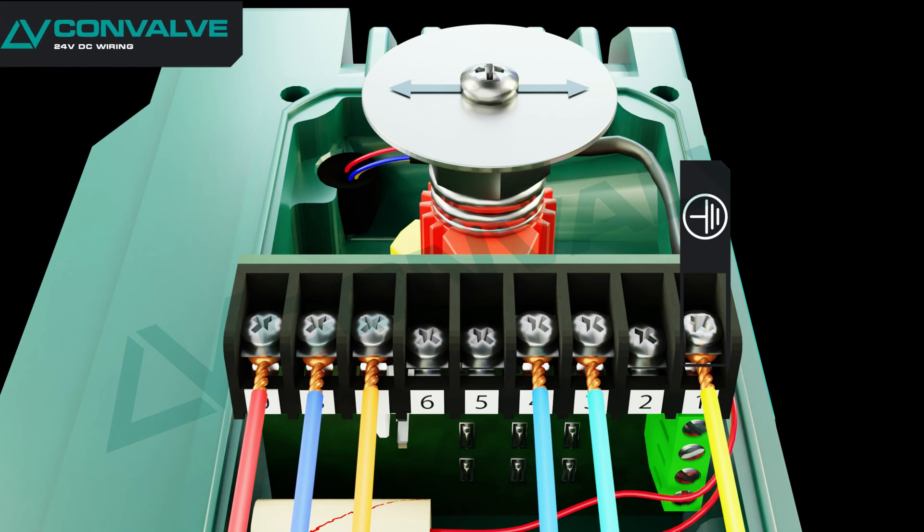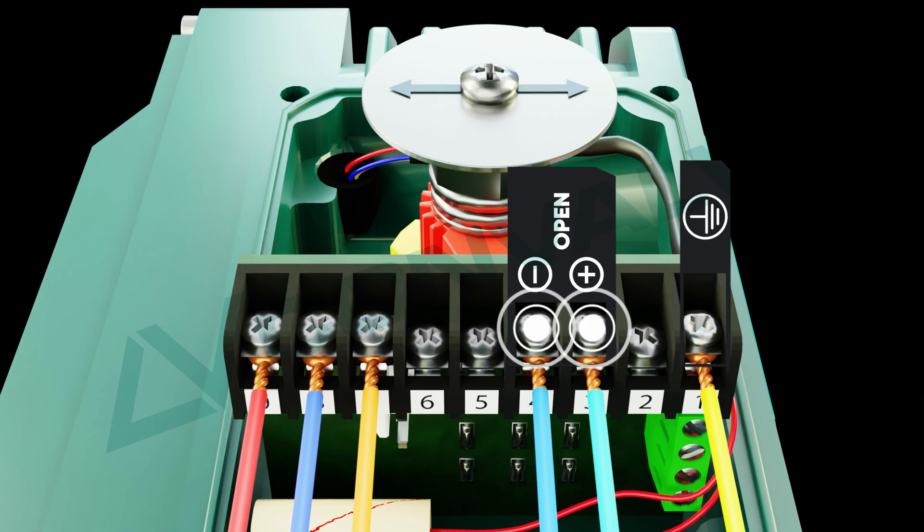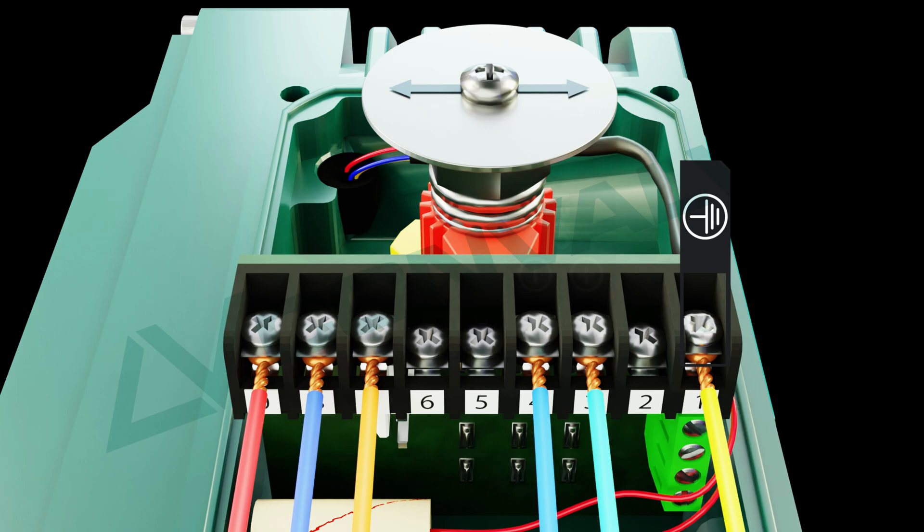For DC voltage units, to rotate or open the actuator in the counterclockwise direction, apply a positive DC voltage to terminal 3 and a negative DC voltage to terminal 4. The actuator will rotate counterclockwise until it reaches the internal limit switch and automatically shuts off.